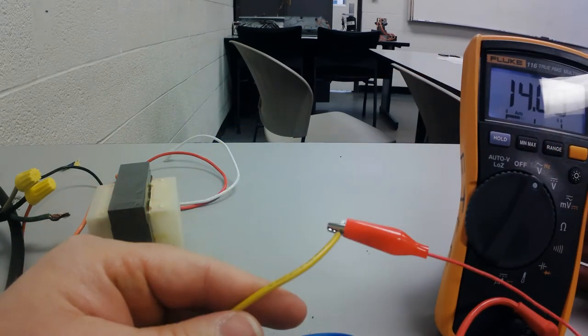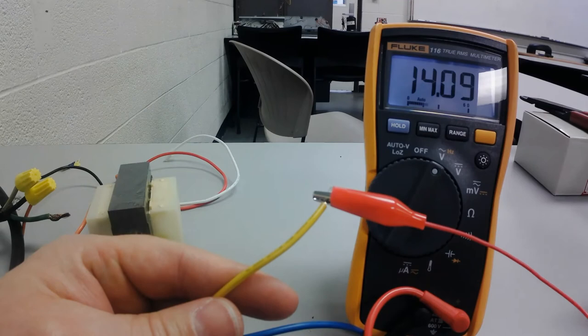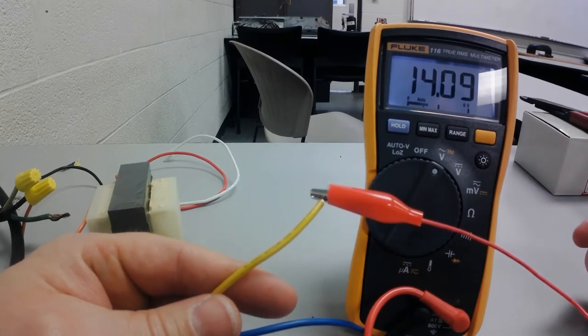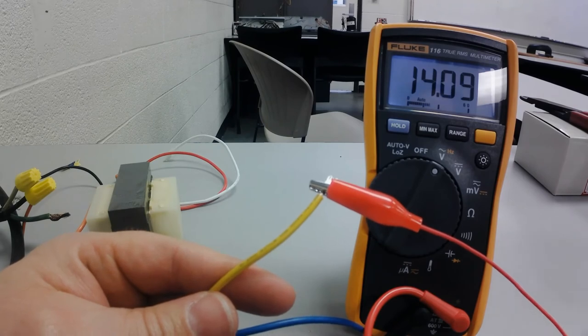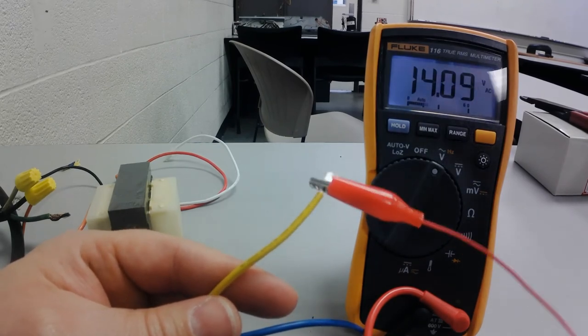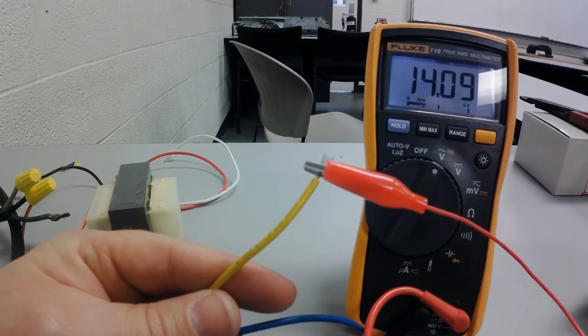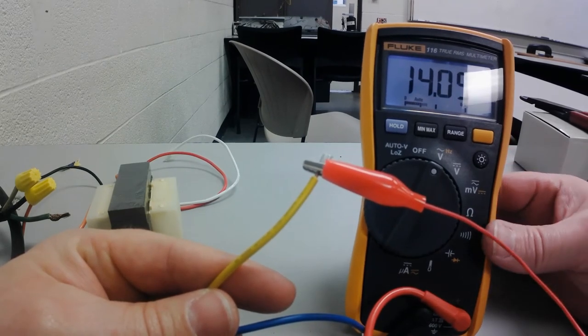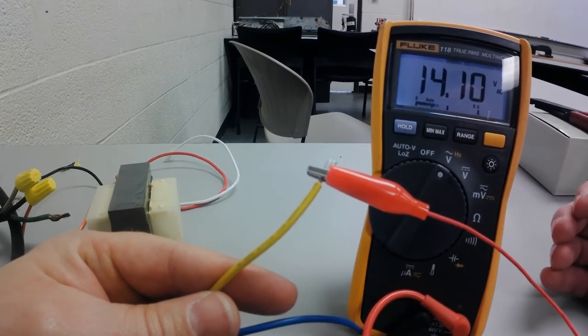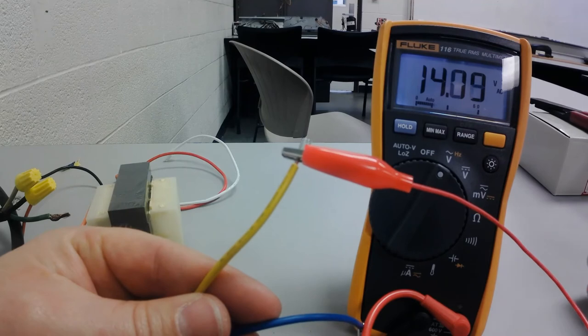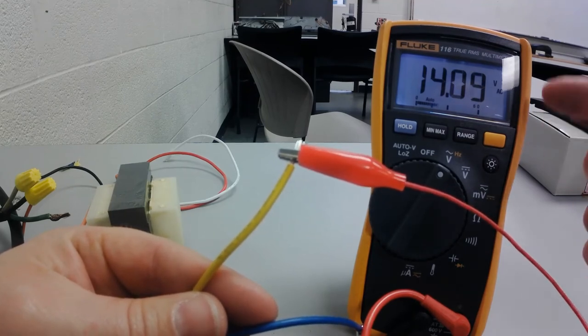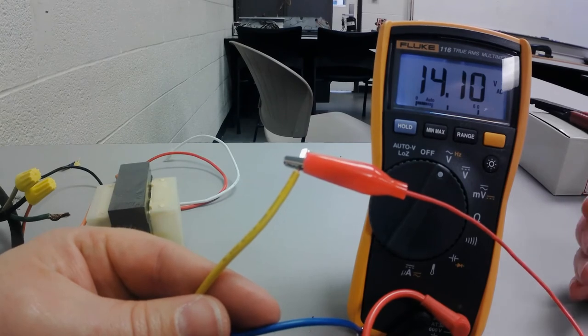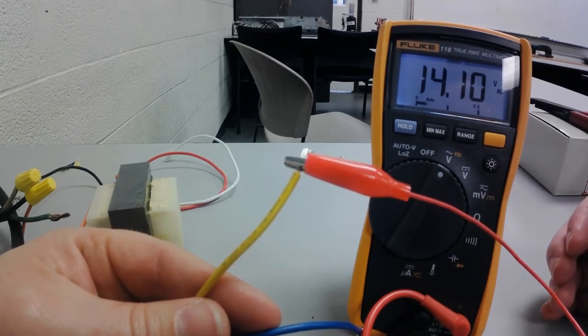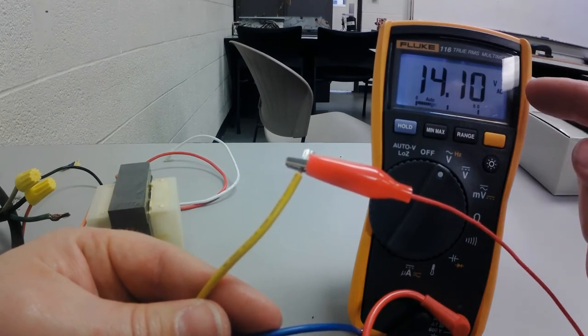So here you can see that I've got my voltmeter set up, and I am putting 120 volts on the primary side of my transformer, but I've tapped it into the 240 volt wiring. So I'm using my orange and the black, which is set up for 240 volts, but I've only put half the voltage in on it. If you put less voltage on the primary of the transformer, then you can expect less voltage out of the secondary. So in my case, I've put half of the 240 on the primary side of the transformer. So if I look at my secondary, you can see that I'm getting half out.